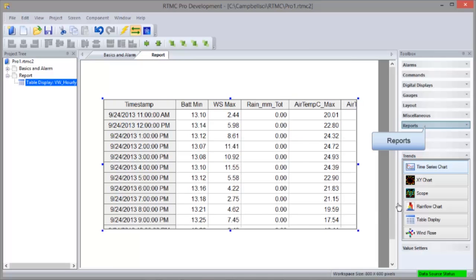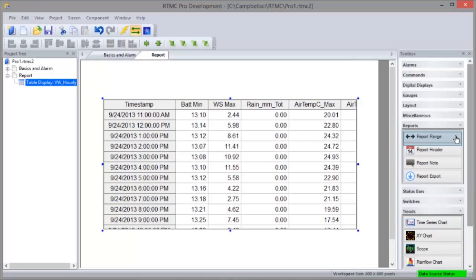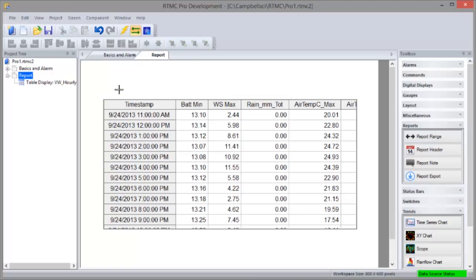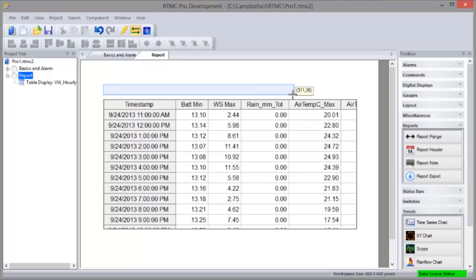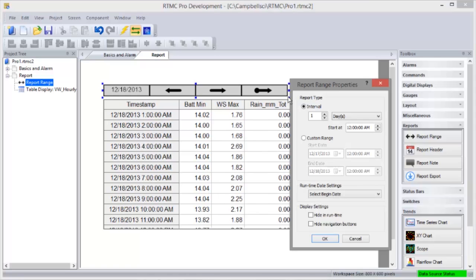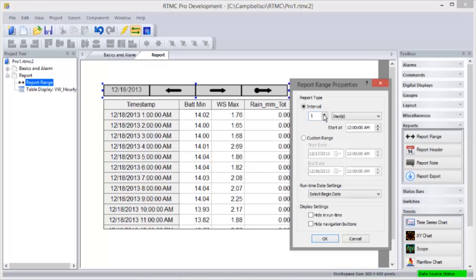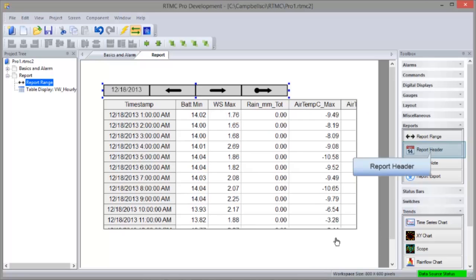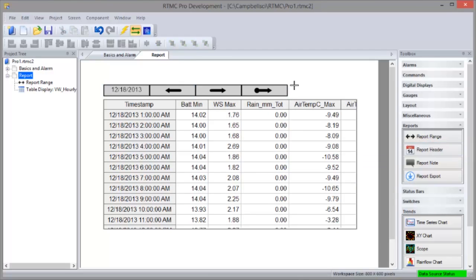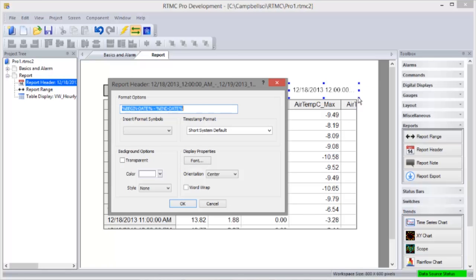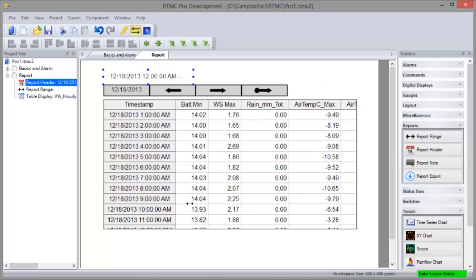Now go to the Reports group. First we'll add the report range. This is what designates the screen as a report. This is where you configure the time ranges of the data to be displayed. It also gives you RTMC runtime options for stepping through the data. My data is stored hourly, so I'll set the interval to one day. Each table will display one day's worth of data. The Forward and Back buttons will step through the data a day at a time. The Report header is optional. It displays the time range currently displayed. The Properties lets you customize the label. The heading fits better up here.